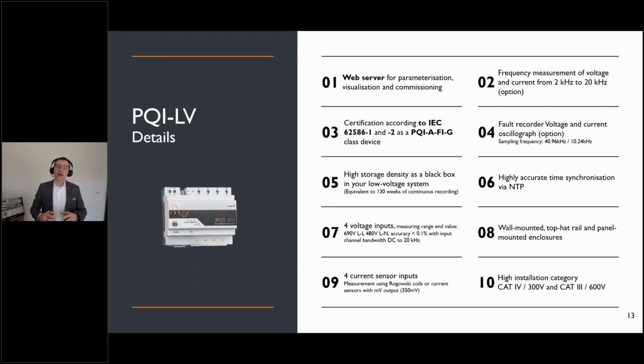From the sensor, current measurements can be done either via Rogowski coils, very easy with an RJ45 plug, or via millivolt outputs of CTs. This is a good thing too, because especially in the low voltage grid, this technology is much cheaper than 1 amp or 5 amp output from normal CT technology.